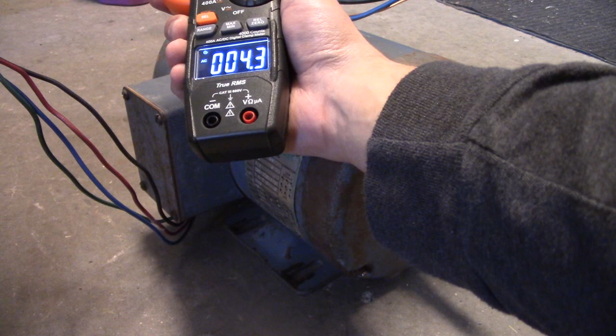If I probe the single phase line right here, I'm pulling 6 amps. I'm going to shut off this motor. You see it goes down to 4.3 amps. That's no load running on a single phase line.